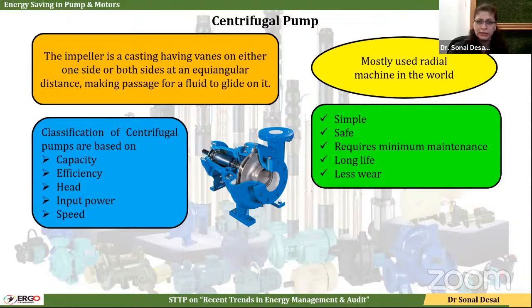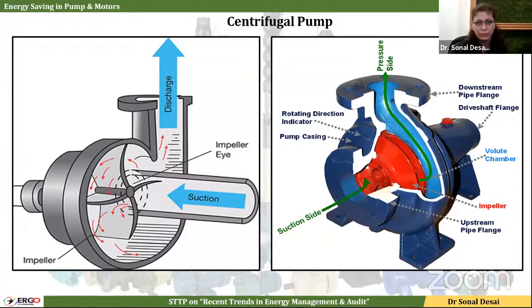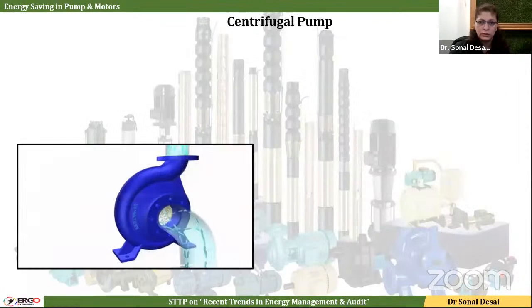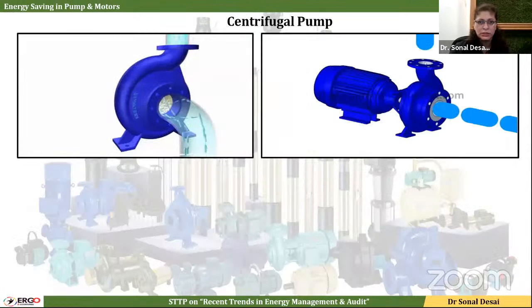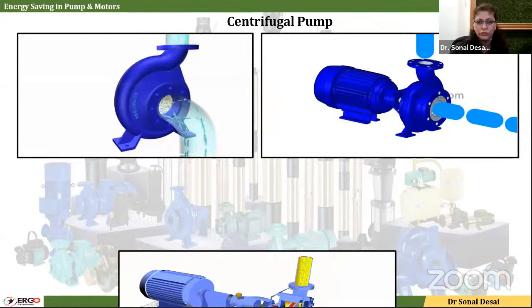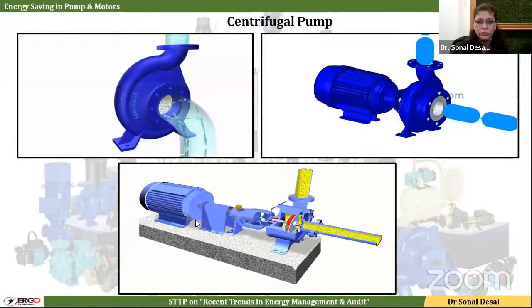Some diagrams and animations are there which explain these pumps. We will just go through them so that how to save energy in them can be realized in a better way. As just mentioned, the center portion, which is housed in this involute casing, is called the impeller. It receives fluid, and the fluid gets energy from this impeller and is then discharged at a higher energy. Let us see some animations. So here is how the function of a centrifugal pump takes place. It's a motor which connects with the hub of this centrifugal pump and pumping takes place.